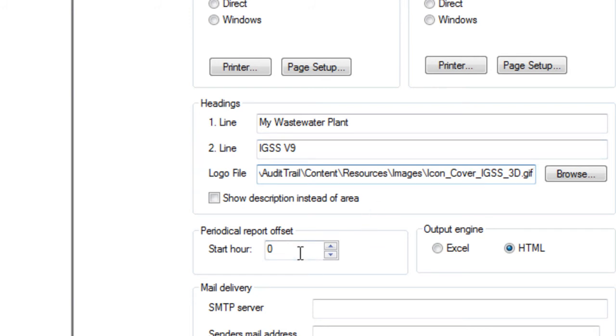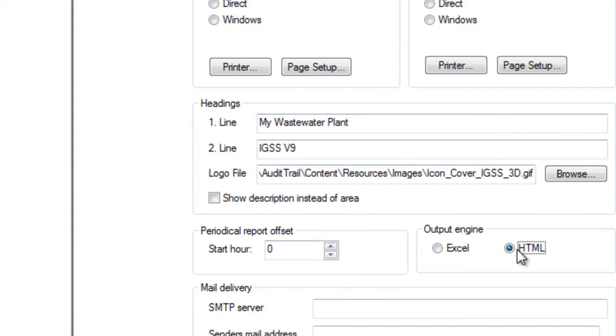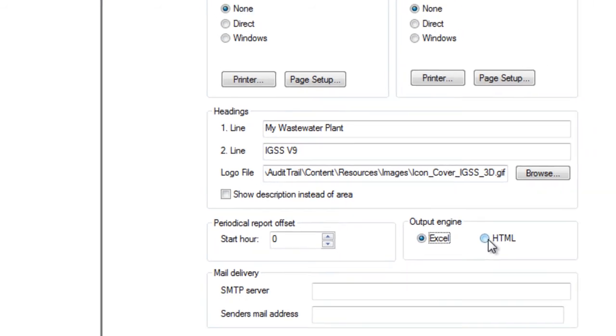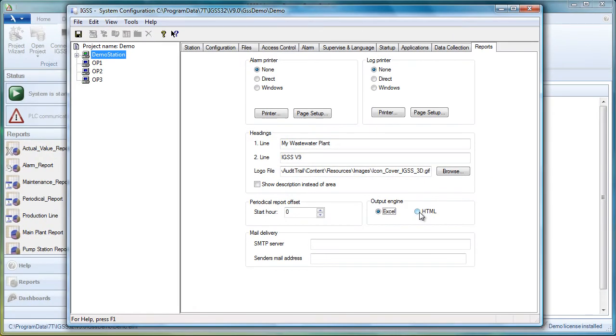Periodical Report Offset means that by default a daily report will be from midnight to midnight. But if you change the start hour, let's say you change it to 6, for example, it will be from 6 to 6. And finally, the output. You can either have HTML, which is the default, or you can have Excel. Remember that if you choose Excel, then all operator stations must have Excel installed.